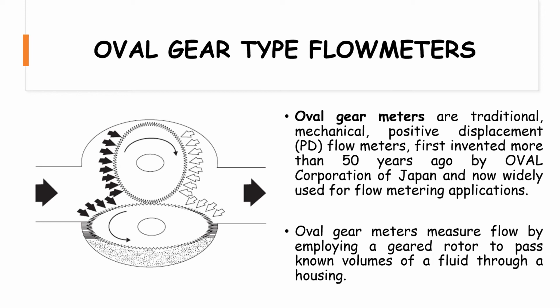So a very precisely adjusted gear pair with the casting forms the measuring element. Therein the flowing medium causes the gear pair to rotate. The rotary motion is scanned by contactless sensors, and since each individual tooth generates a pulse, this results in a very high resolution.